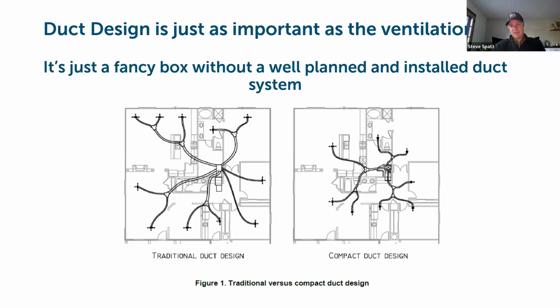So this is critical to the success of the system, and it's critical that this is something that's thought out and designed into the building from initial design and concept stage. It's not something to be thought of after the fact or just kind of fit into the building once the structure is built. Really, you need to be understanding where is the equipment going to go, what duct sizes do you need to move air effectively to the different rooms it needs to get to, where do those ducts need to go, what framing considerations need to be made to allow for that. So really, these things need to be accounted for at design stage.